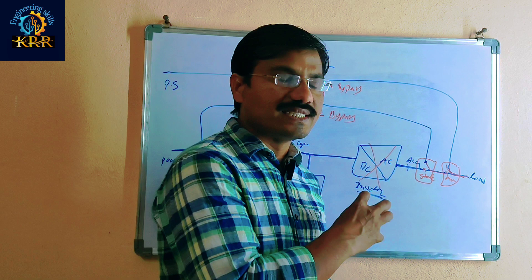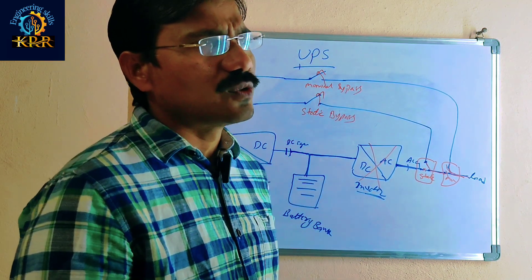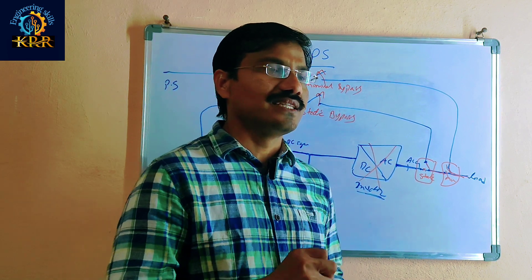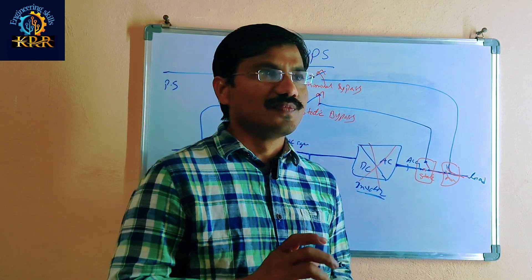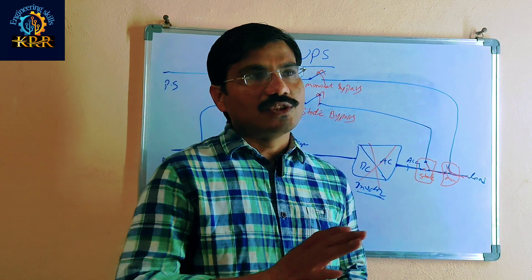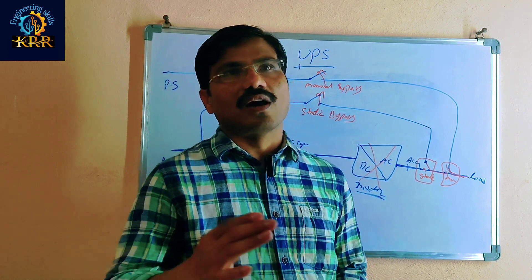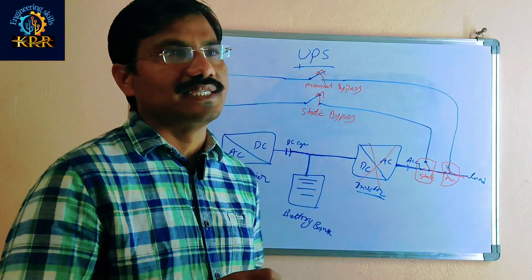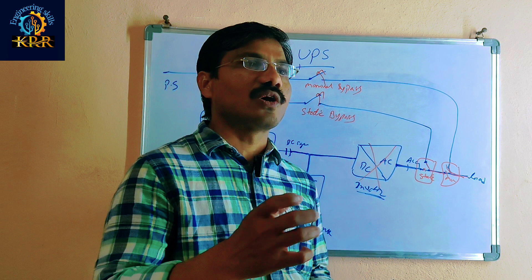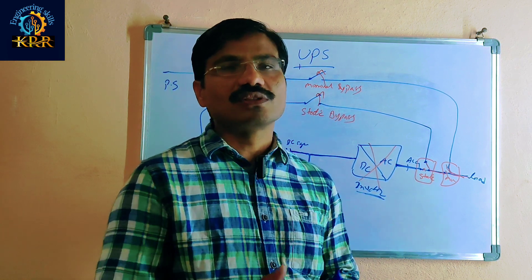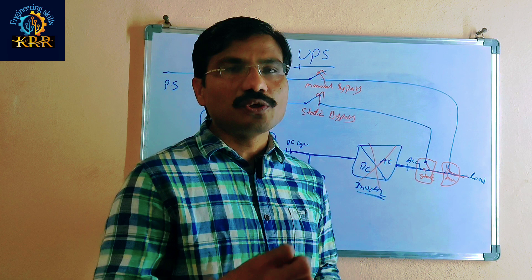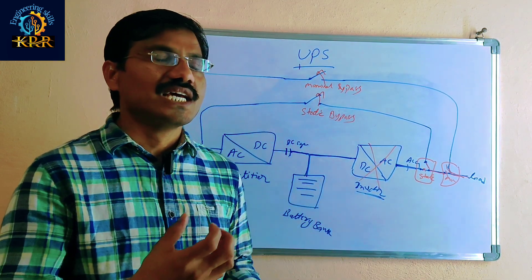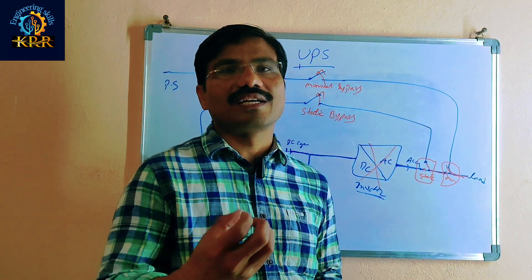One more device also is there inside this UPS: the isolation transformer. The use of the isolation transformer in UPS is: first, isolation of the neutral output from the source output; second, it limits the fault current at the downstream level; third, it reduces generated harmonics — it blocks the triplen harmonics.